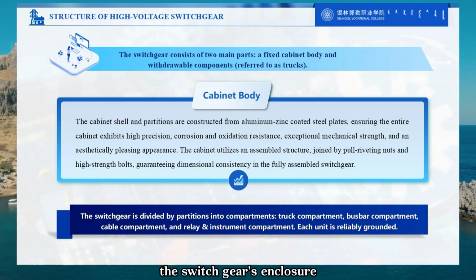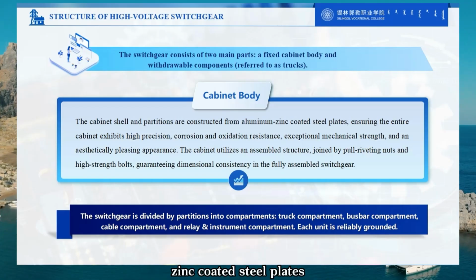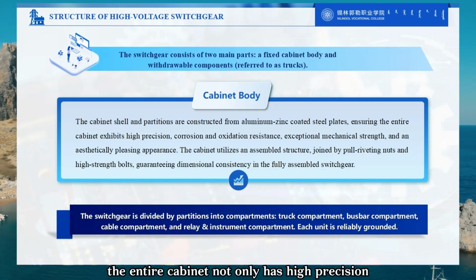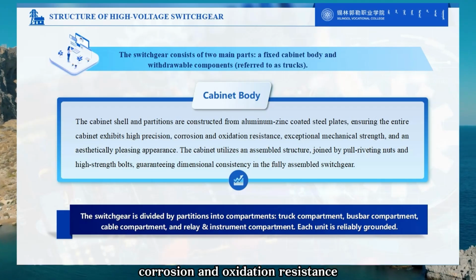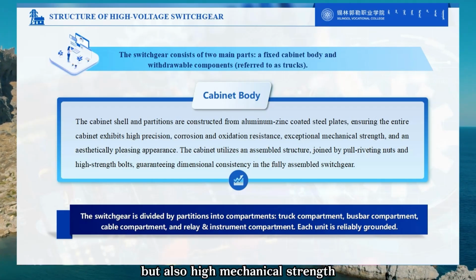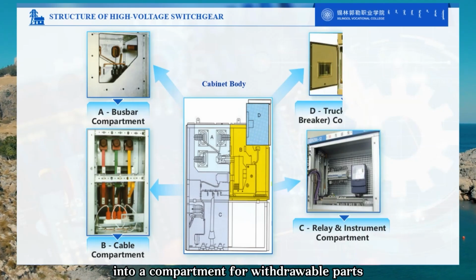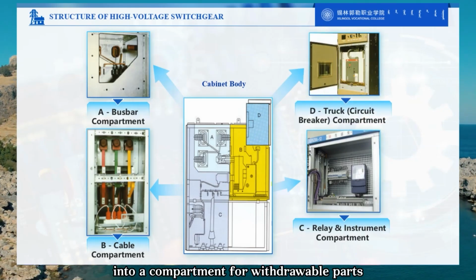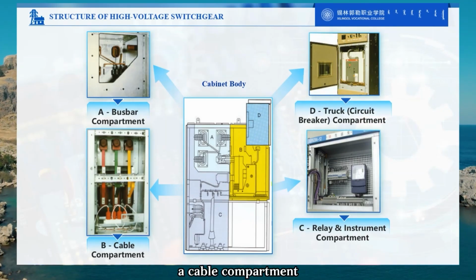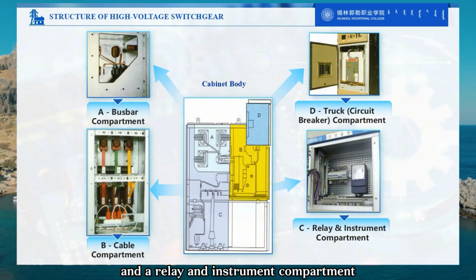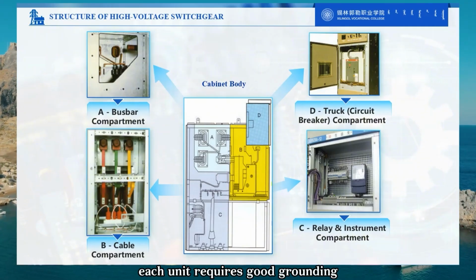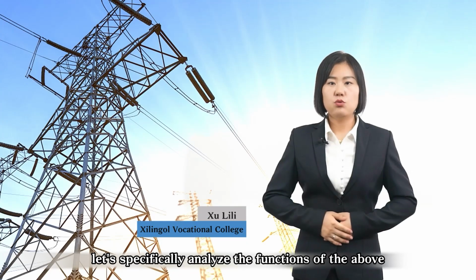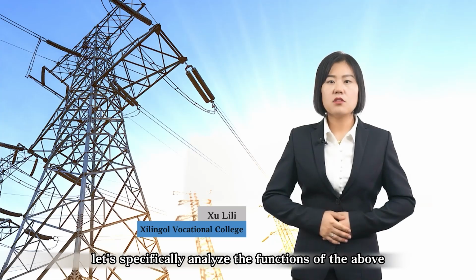The switchgear's enclosure and partitions are made of aluminum zinc-coated steel plates. The entire cabinet not only has high precision, corrosion, and oxidation resistance, but also high mechanical strength and an attractive appearance. The switchgear is divided by partitions into a compartment for withdrawable parts, a busbar compartment, a cable compartment, and a relay and instrument compartment. Each unit requires good grounding. Next, let's specifically analyze the functions of the above 4 parts.